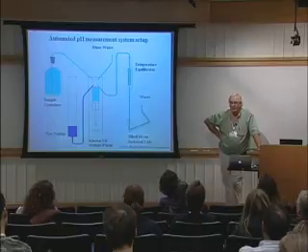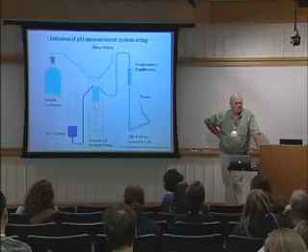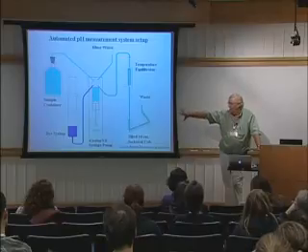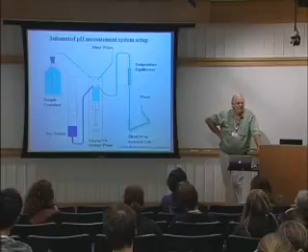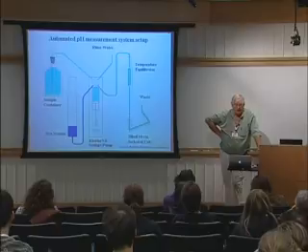It uses about 50 mils at most of your sample. We can make it less. It's a matter of how thoroughly you want that flushing to go, because it doesn't have to be that thorough because of this rinse water line on it.